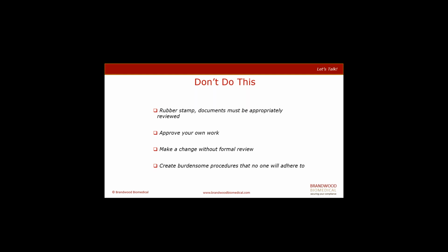Never approve your own work, as obvious as that may seem. Making a change without formal review has been brought up in many a warning letter and many 483s. And most importantly, I guess, is don't create burdensome procedures that no one will adhere to.